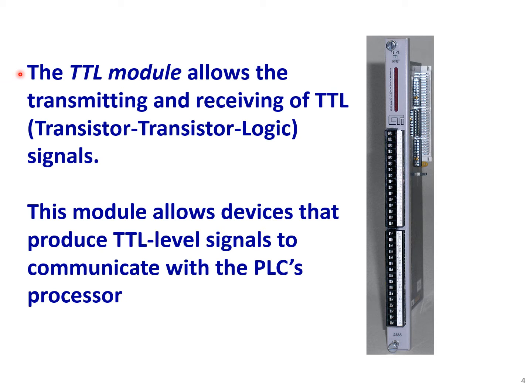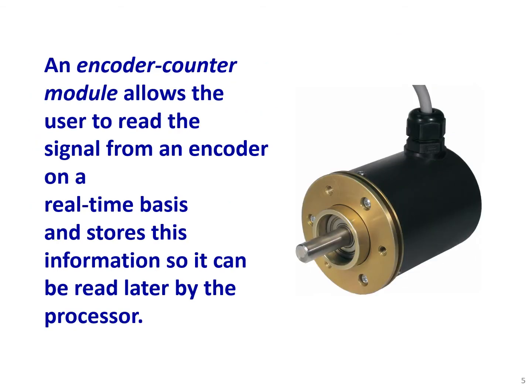Another special module is the TTL module, which allows the transmitting and receiving of TTL, or transistor-transistor logic, signals. This module allows devices that produce TTL signals to communicate with the PLC's processor. It's a common and useful type of special device for accepting TTL signals. An encoder counter module allows the user to track the signal from the encoder on a real-time basis and stores this information so it can be read later by the processor.